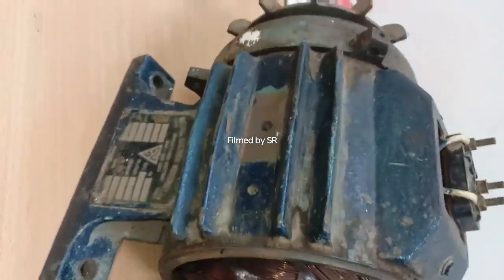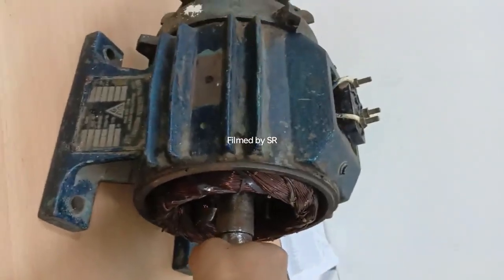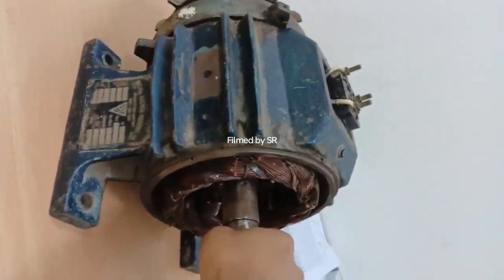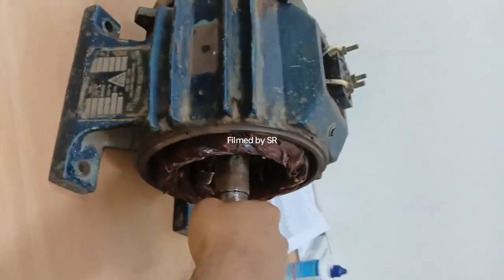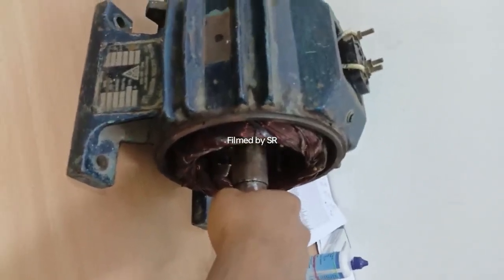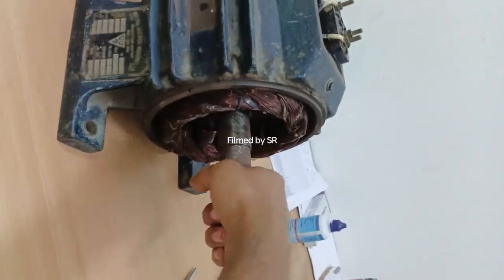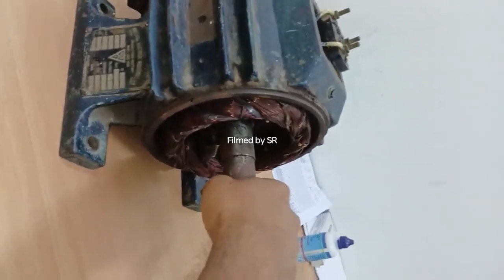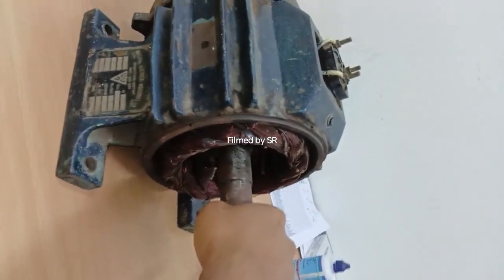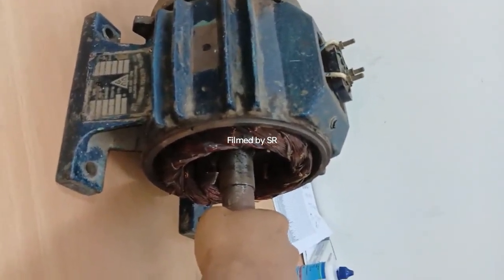One is this: if you can reduce the rotational speed of this shaft, then you can effectively change the rate of change of flux. Even if you allow the same current flowing through your rotor and producing the same amount of electromagnet, the same magnetic field strength, if you reduce this rotational speed, then you can curb that dφ/dt, and in that process reduce the EMF induced in the stator coil, and thereby reduce the current flowing through the stator winding.